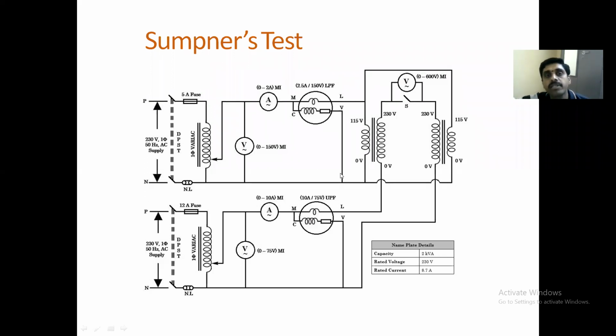Coming to Sumpner's test, it is also called the back-to-back test. This test is mainly used to find out the temperature rise in transformers. If you take a small transformer, you can load the transformer and conduct the test. Full load you can apply and find out the temperature rise of the transformer.